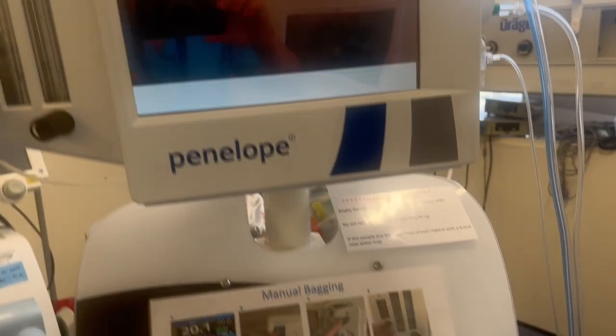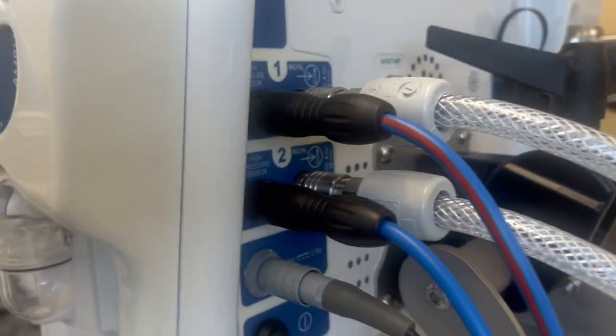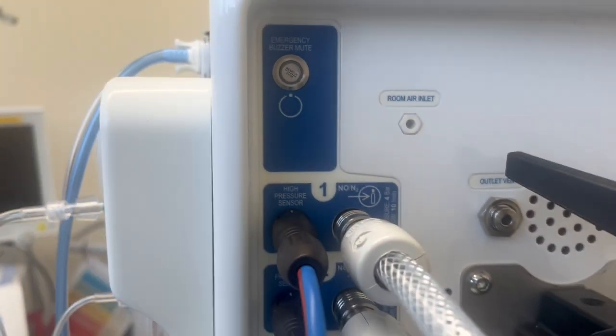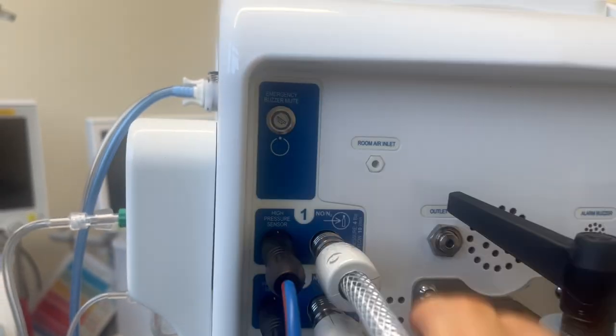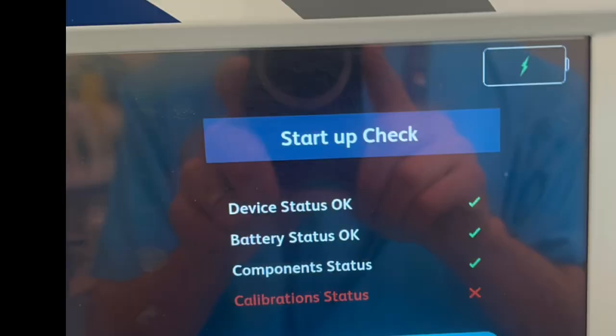As the machine boots up, the emergency buzzer alarms. This can be reset at the back of the machine, top left. The machine now checks some internal components. If any of these are in red with a cross, the machine shouldn't be used. You can clearly see that the calibration status is in red. This means that the high-level calibration done by the ICU technicians has timed out and the machine shouldn't be used.